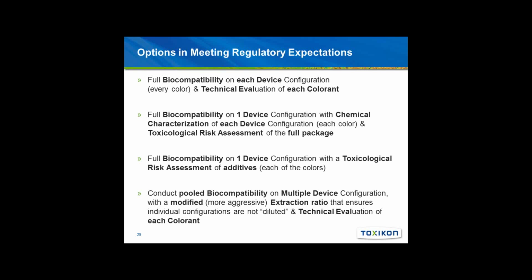Well, you can conduct your full biocompatibility on each device configuration, because the one that's red and the one that's blue and the one that's yellow are not all the same because of that colorant, that chemical compound, and then have a technical evaluation of each colorant. Now, I'm not going to say that that's the most effective way to do this. I'm just saying that that's one of the options that could meet your regulatory expectations for your device. The next one is to do full biocompatibility on one device configuration and chemical characterization on each device configuration. That would be each of the different colors that my device comes in.